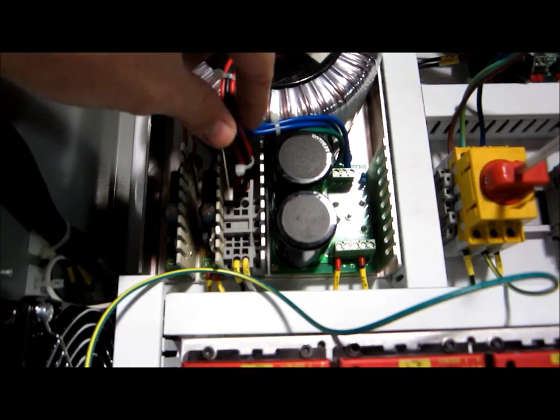Comes through here. This solid state relay is mounted on a heatsink, which is why it's so tall. So I've already got my line in, and then T side, consumer side, I'll wire directly to this solid state relay. I won't even stop at a field terminal. I just didn't have enough space. So that's the AC side. AC comes up to your power supply. This is an 11 or 12 amp power supply. I got a 56 volt DC output, even though it comes out really at 54.